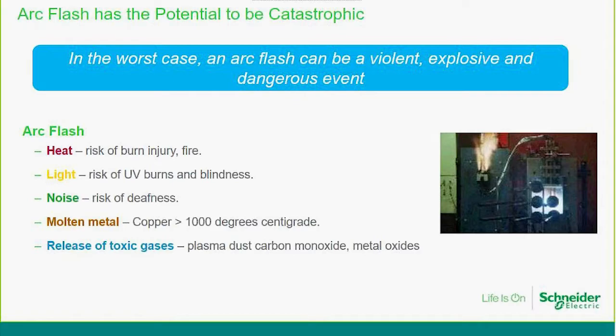Molten metal, these are the secondary things now, is unfortunately the vaporization of the material involved in that fault condition. We're talking about materials that could be at greater than 1,000 degrees centigrade. And depending on how close you are, you could have that heading towards you at a very, very rapid speed. There's also the release of toxic gases, plasma dust, carbon monoxide and metal oxides. It's whatever is actually in the material that's been vaporized. So it is actually a very dangerous event.